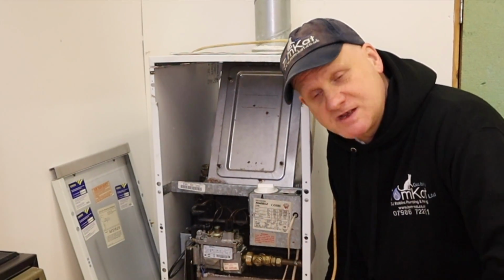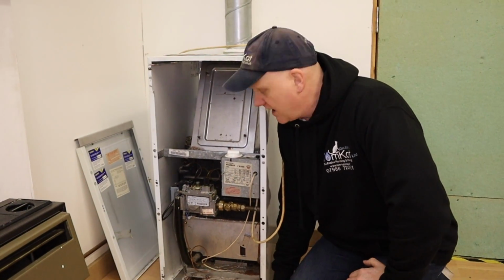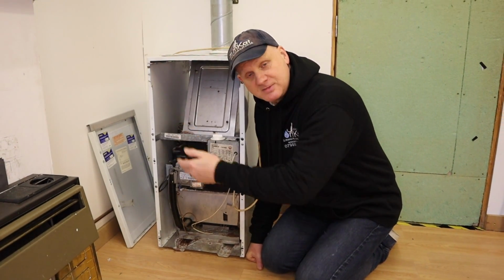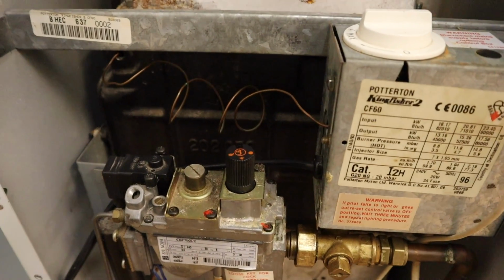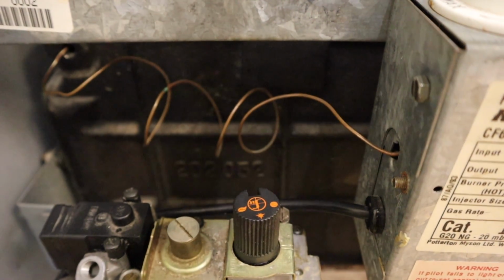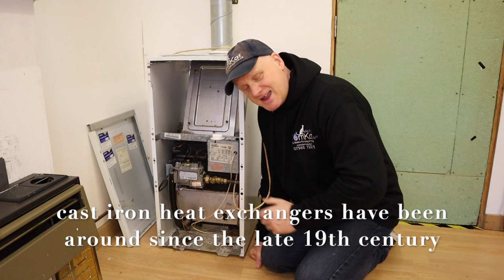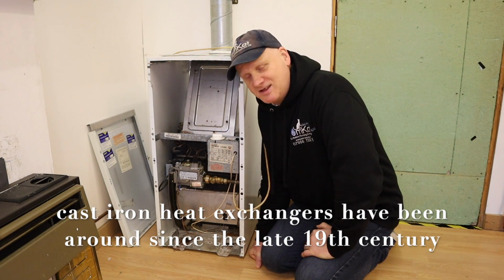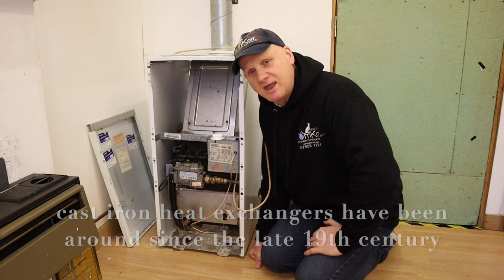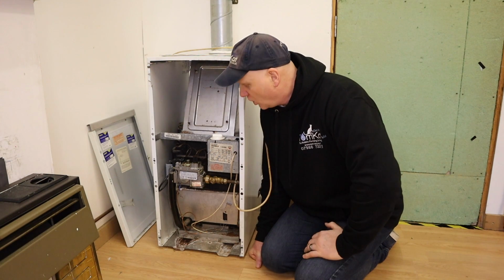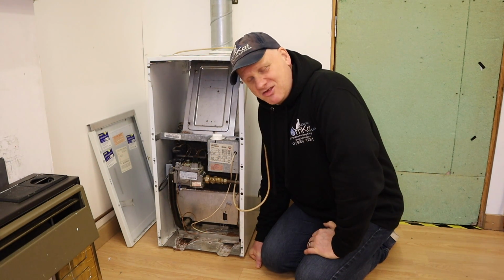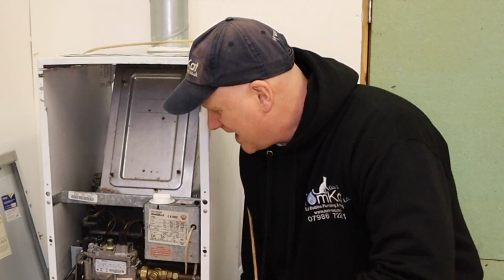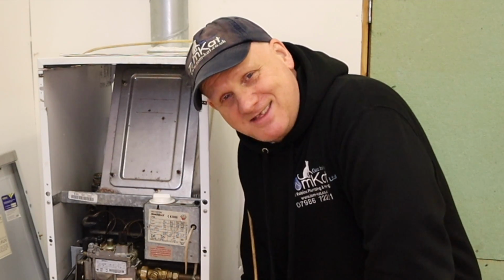Now let's have a closer look at these heat exchangers, and let's start off at the beginning and look at cast iron heat exchangers first. Now, this Potterton Kingfisher 2 floor standing open flued boiler has a cast iron heat exchanger, which is just located here. Now, cast iron heat exchangers are composed of iron, carbon, silicon, and may contain traces of other elements. Traditionally, cast iron heat exchangers dominated the UK market for decades, and you may still find homes and businesses in the UK where they're heating their premises and water by boilers using cast iron heat exchangers. There shouldn't be. Now, in my opinion, there should be no boiler in the UK with a cast iron heat exchanger, because they're just not efficient enough for our modern living.